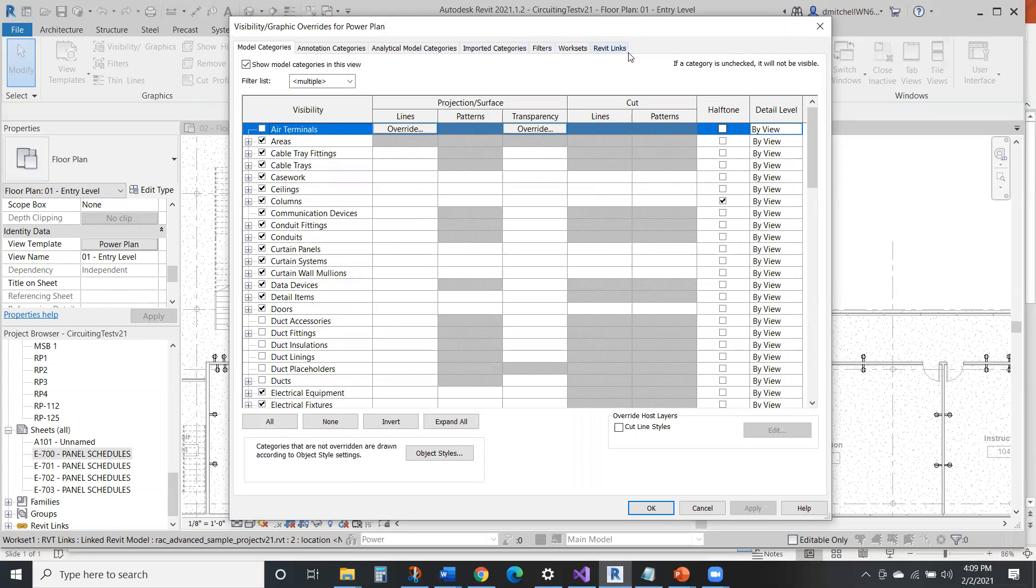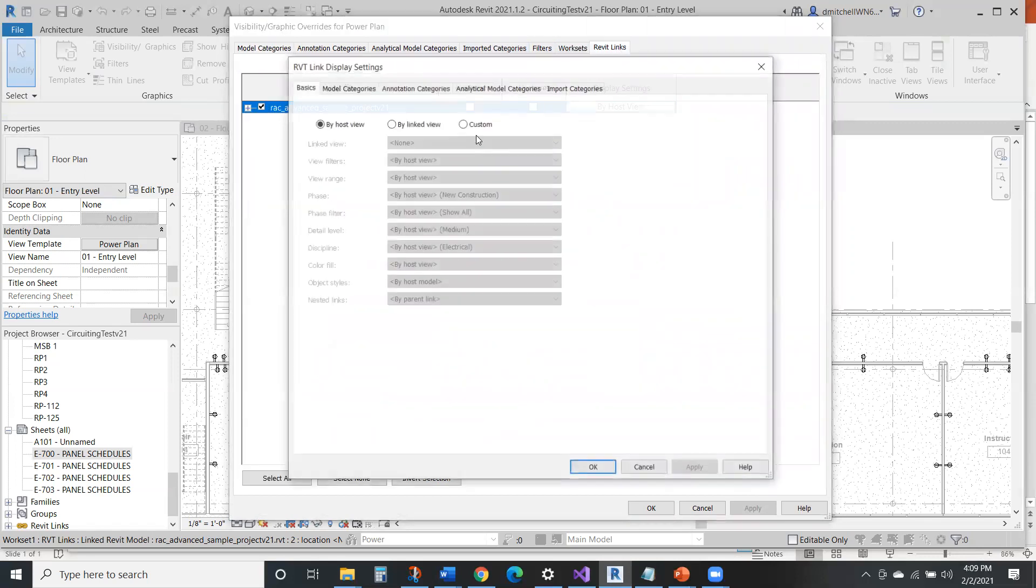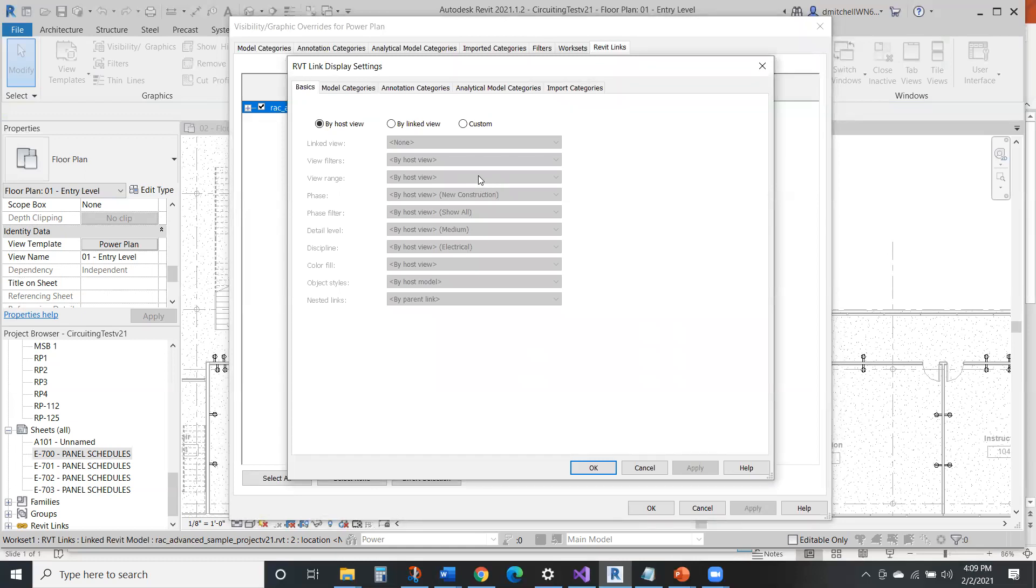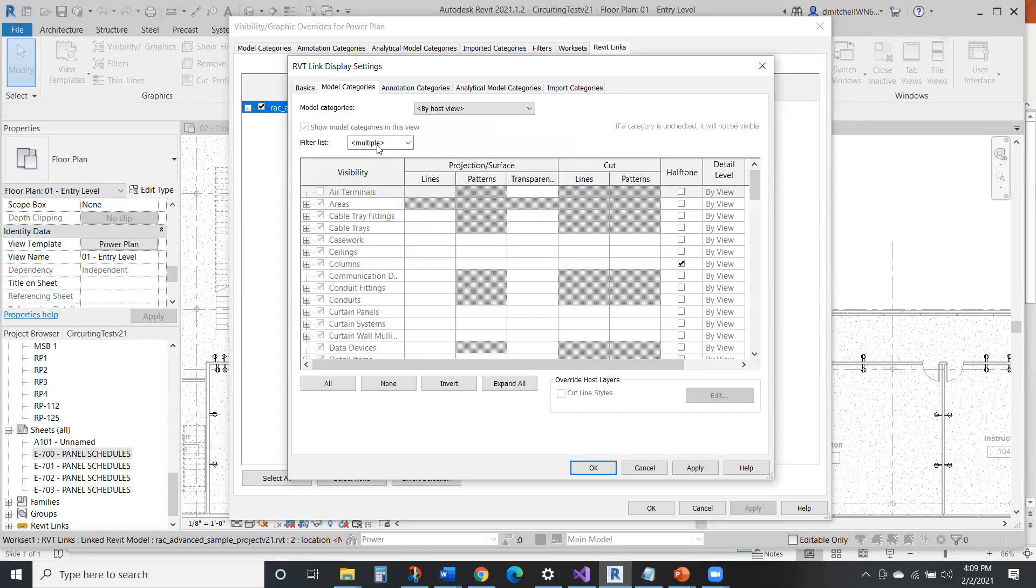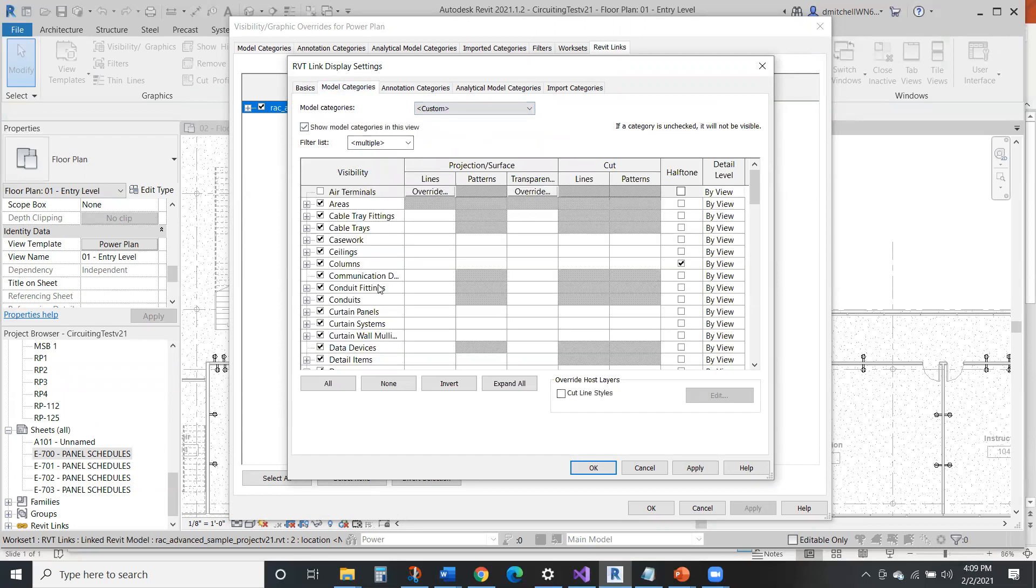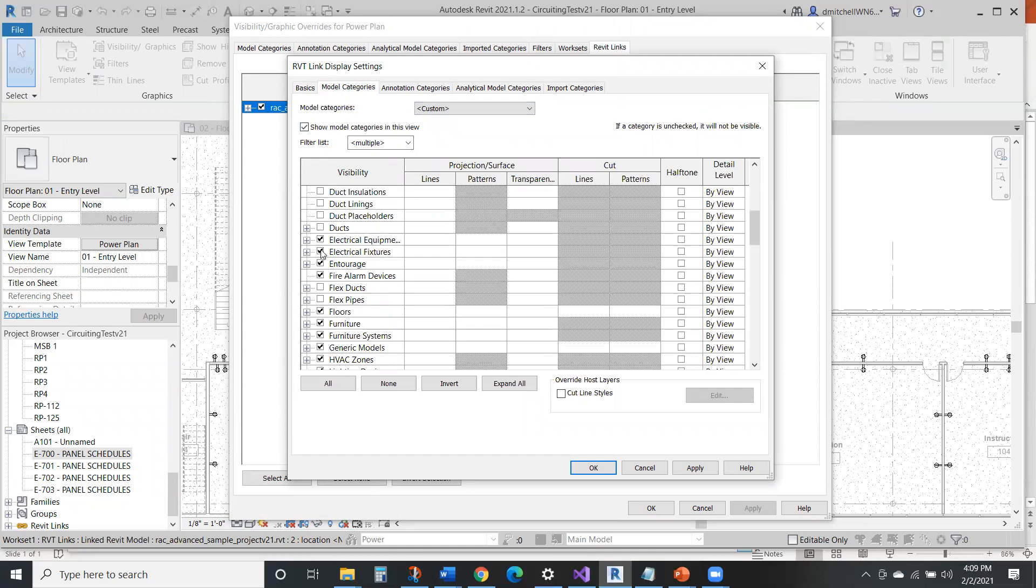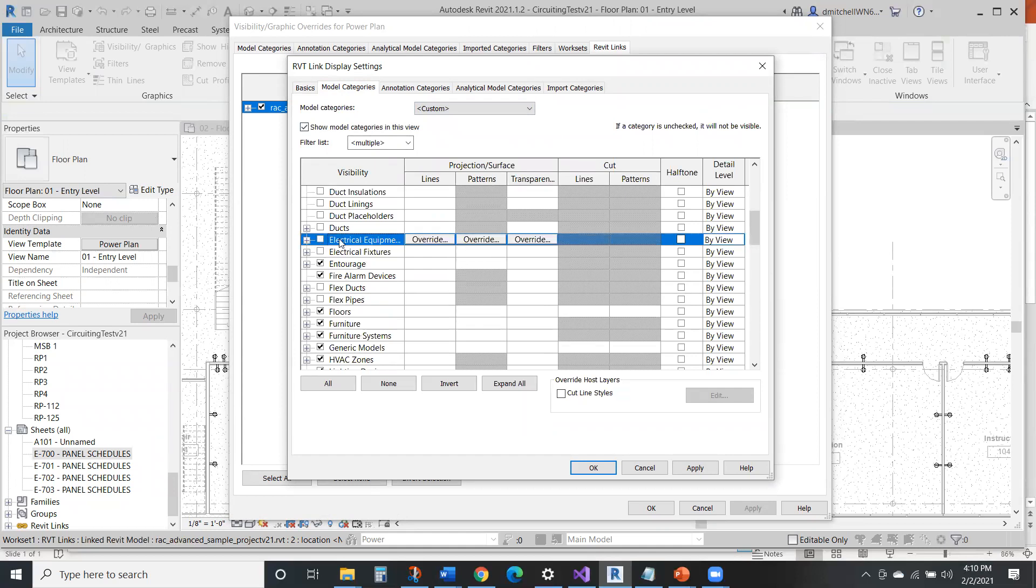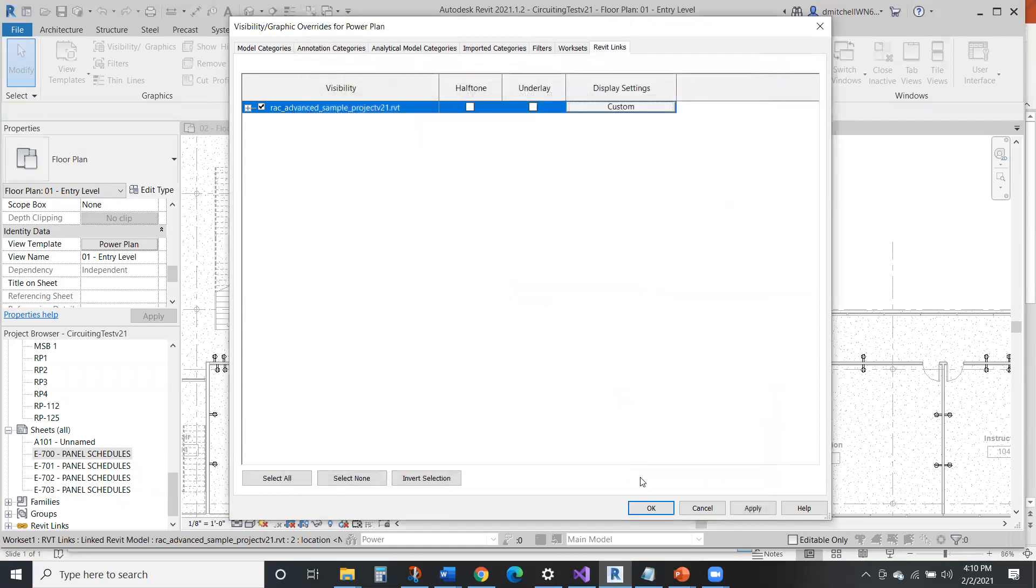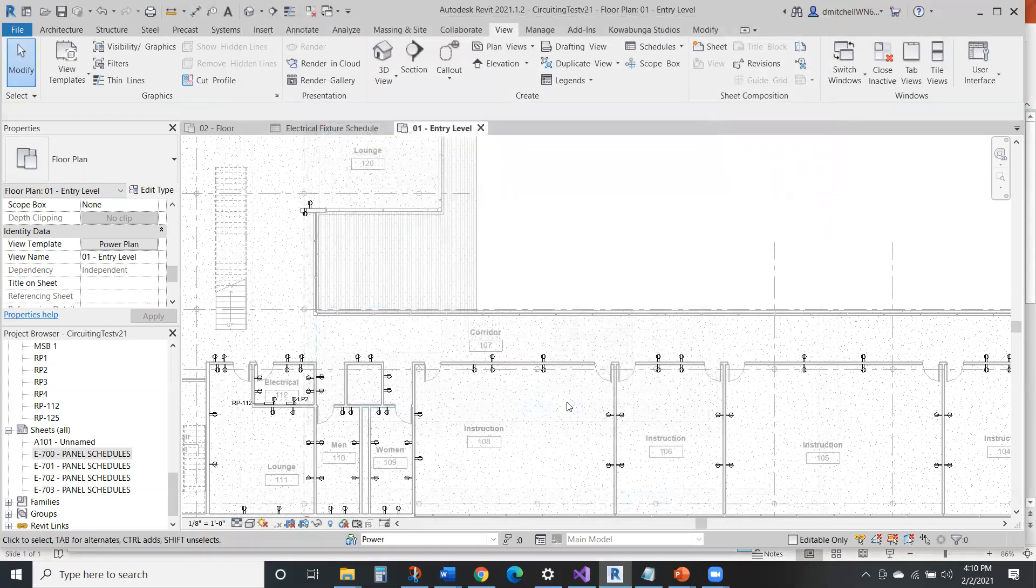And then really the other thing that you end up needing to do is basically hiding stuff in linked models. So if the architects are also showing like receptacles or lights or other content that you don't want to see in that particular view. Like you want your outlets, your lights to show up, but not from the architectural model. So you come in here and hit custom, then you can hit custom here. And then hide all the stuff that you don't want to see from like the electric or from the architectural model. So that's the other way to do it. I find that's much more effective than the worksets.